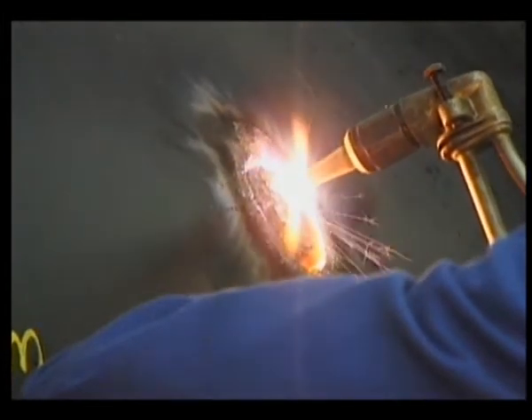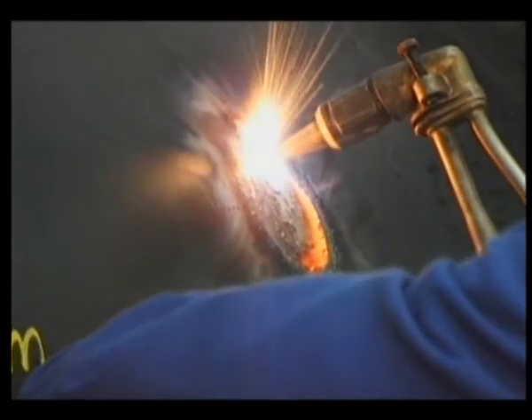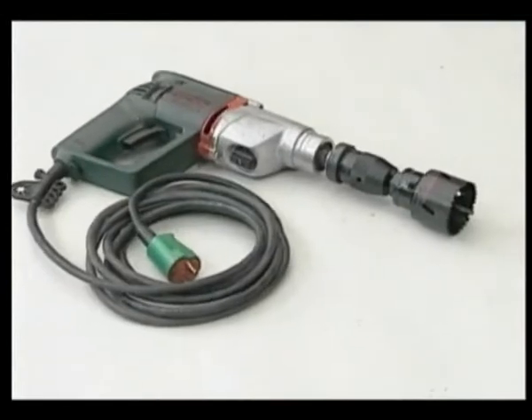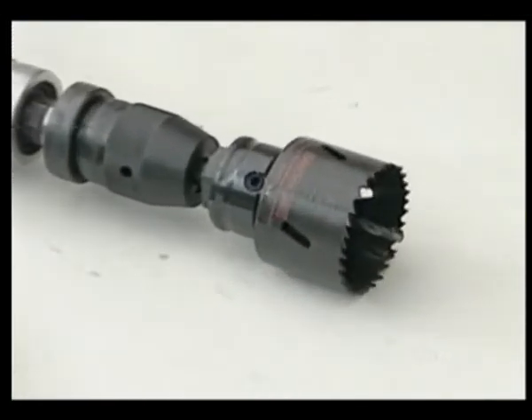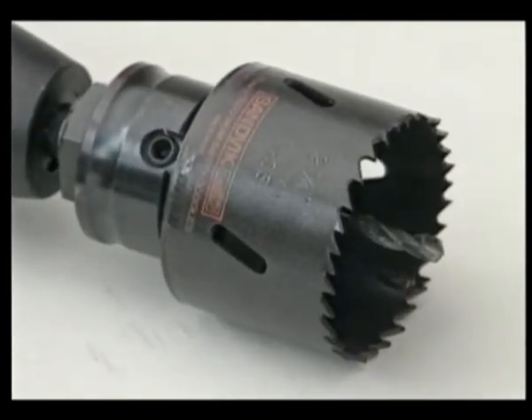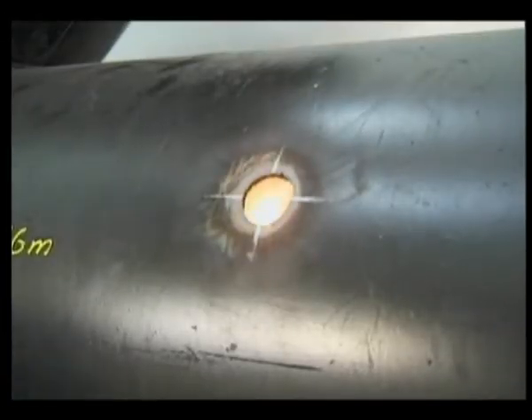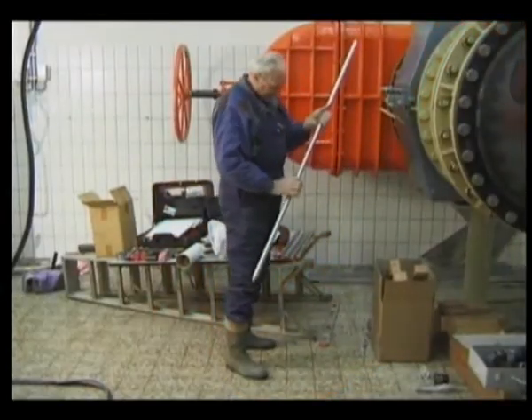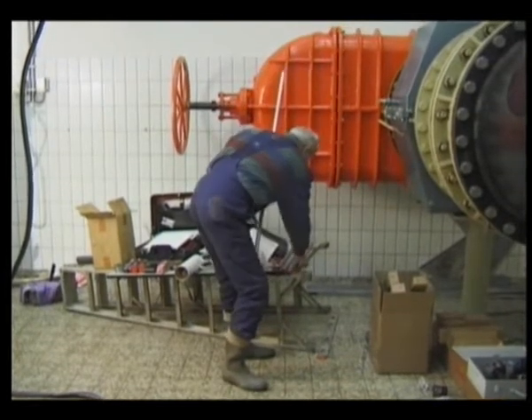The holes can be made with a fire torch, or with a special hole saw as shown here. Which method you use depends on the pipe material you work with. The next step is mounting the parts to hold the ultrasonic transducers. To ensure that the ultrasonic transducers will be aiming at each other, alignment rods are used during installation.